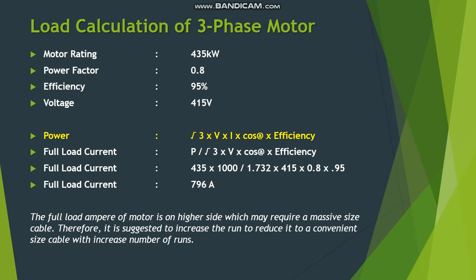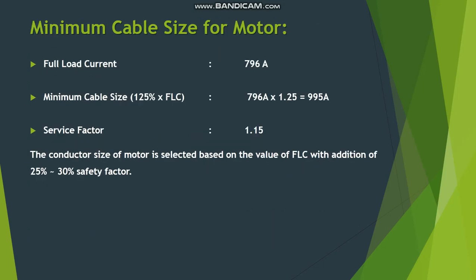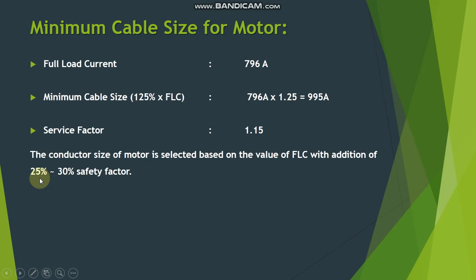The full load current of this motor is on the higher side, which may require a massive cable size. Therefore it is suggested to increase the number of runs rather than reduce to a single convenient cable size. After calculating the full load current, we define the minimum cable size by adding a safety factor. Some designers use 25% and some use 30-35% safety factor on the full load current.